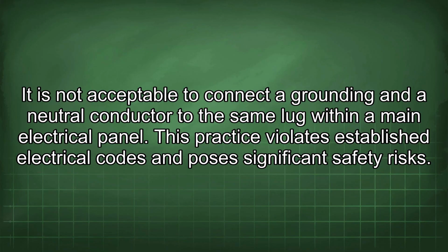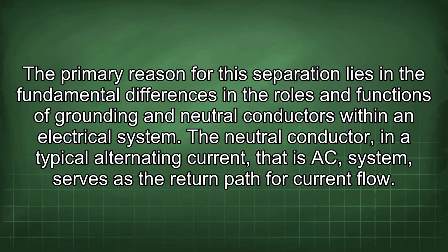It is not acceptable to connect a grounding and a neutral conductor to the same lug within a main electrical panel. This practice violates established electrical codes and poses significant safety risks. The primary reason for this separation lies in the fundamental differences in the roles and functions of grounding and neutral conductors within an electrical system.